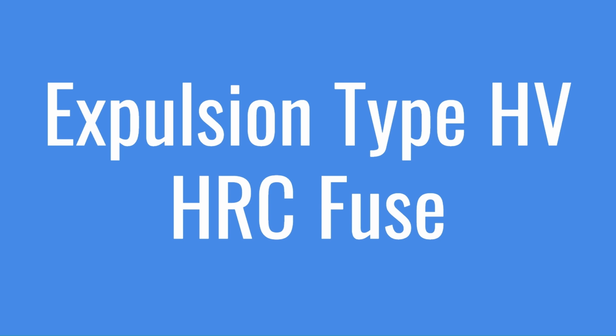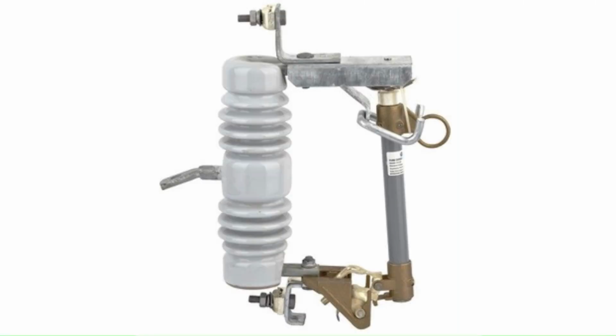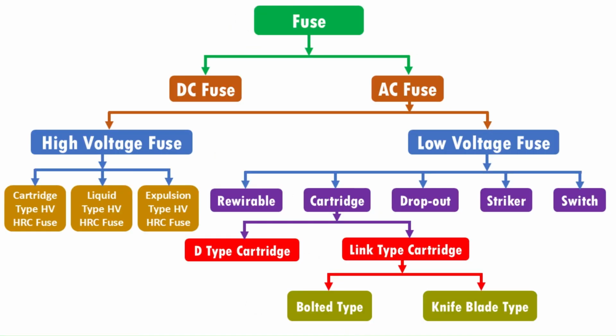Expulsion type fuses are widely used for the protection of feeders and transformers because of their low cost. It is developed for 11 kV and their rupturing capacity is up to 250 MVA. Such type of fuses comprises a hollow open-ended tube made of synthetic resin bonded paper. The fuse elements are placed in the tubes and the ends of the tubes are connected to suitable fittings at each end. The arc produced blows off the inner coating of the tube and the gases formed extinguish the arc. So friends, these are the different types of fuses.